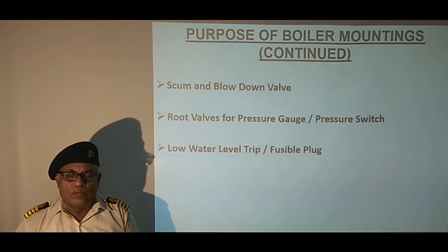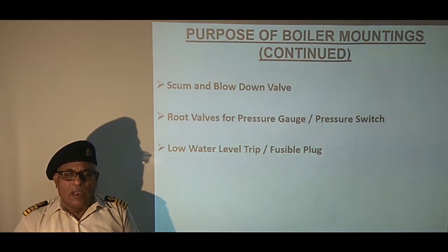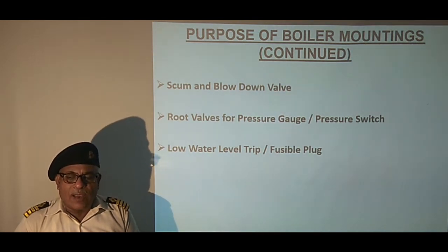Next we have is the low water level trip or fusible plug. Purpose of low water level trip is to stop the boiler when water level is dangerously low or very high, which is achieved by cutting off the fuel supply to the burner. Operation of low water level trip will be discussed in details later.